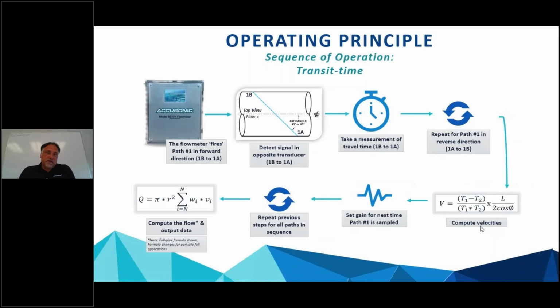The sequence of operation of the flow meter is such that we have a series of transducers and cables that connect up to the flow meter, and we actually transmit at a fairly high voltage. It's about 800 volts DC, but it's only a microsecond wide, so it's a very short, quick pulse. So we basically send the transmit pulse through the transducer and into the cable. The ceramic inside that transducer excites and sends a sound wave out. So that comes through the mating transducer, which would be the downstream transducer in this case, and that goes through the cable and back up to the flow meter. We actually record that time and then we reverse it.